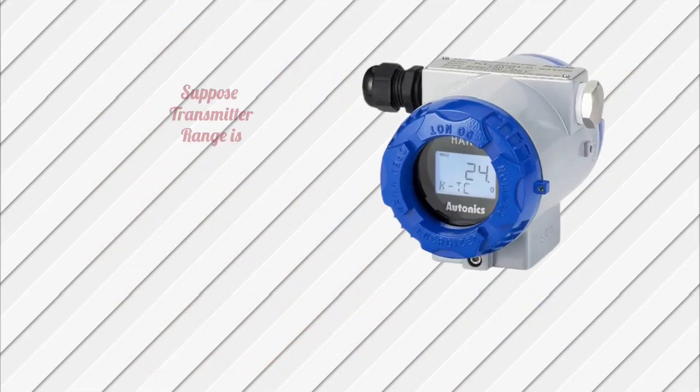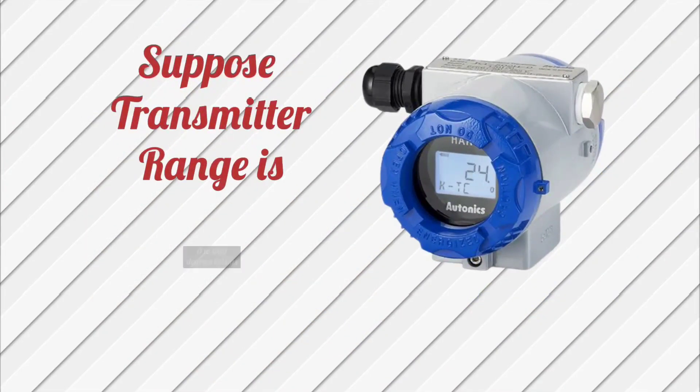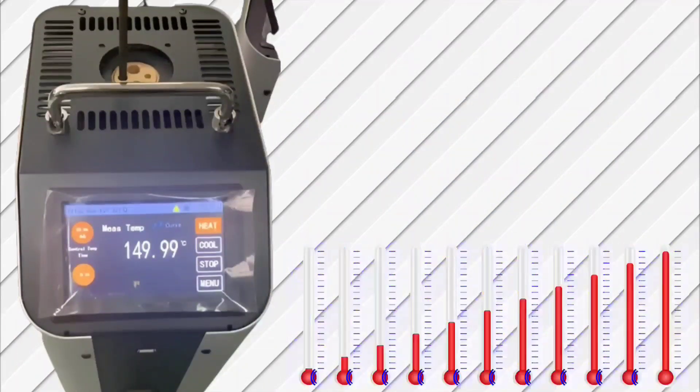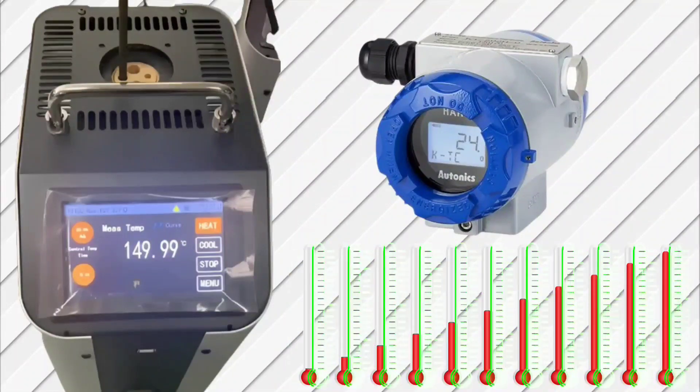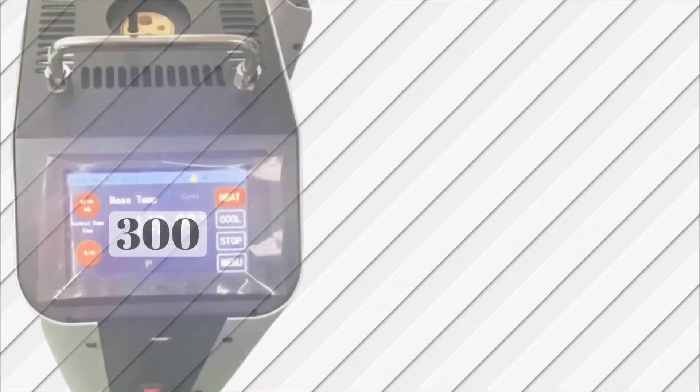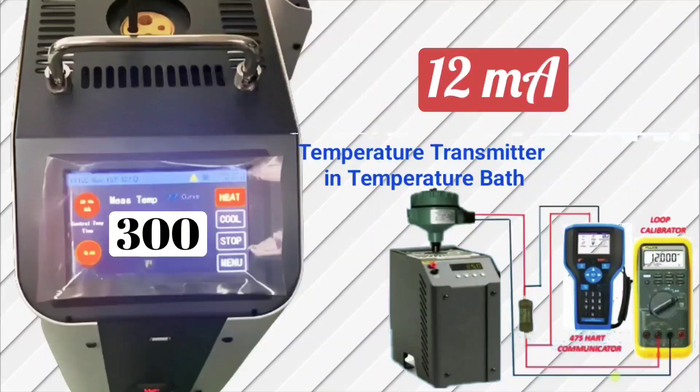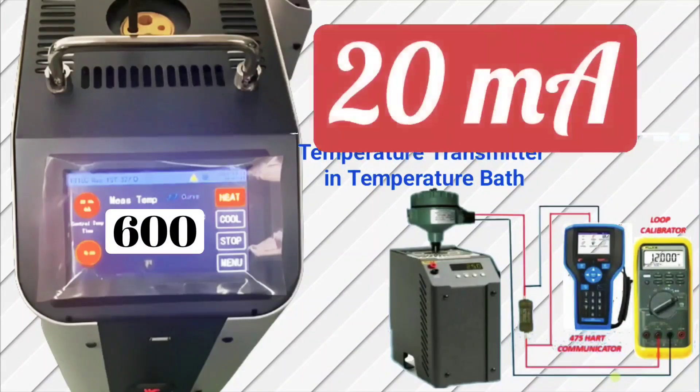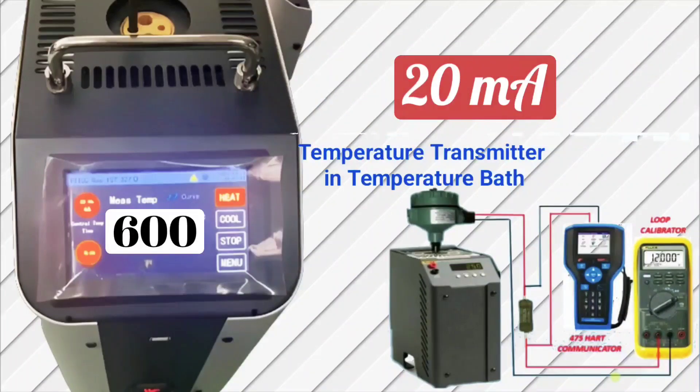Suppose the range of transmitter is 0 to 600 degrees Celsius. At different temperatures, we will check what will be its output. Like at 300 degrees Celsius, the output should be 12 mA. At 600 degrees Celsius, the output should be 20 mA.